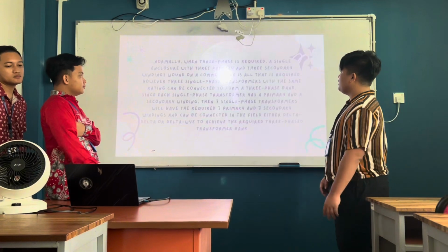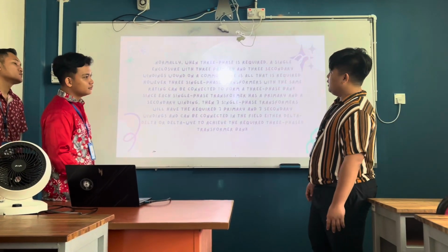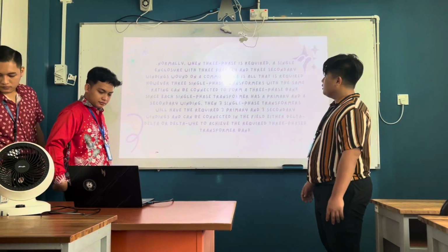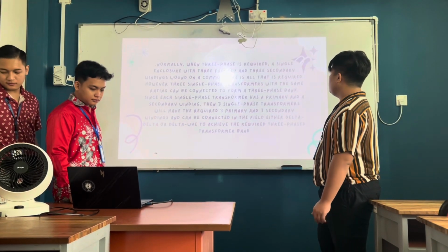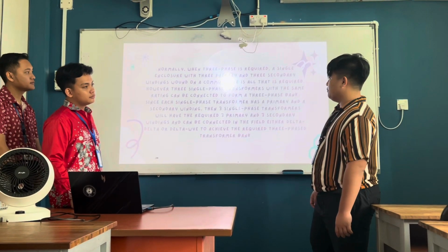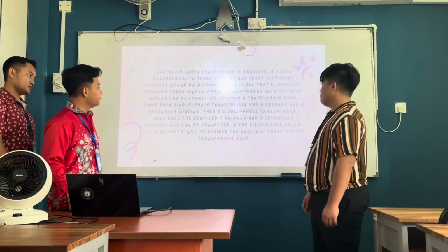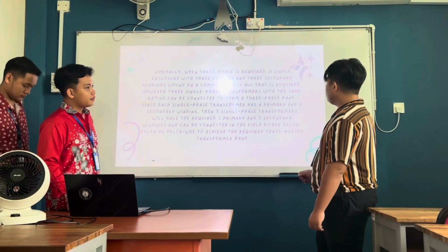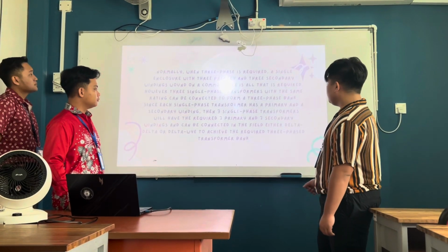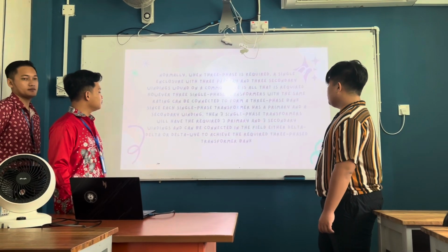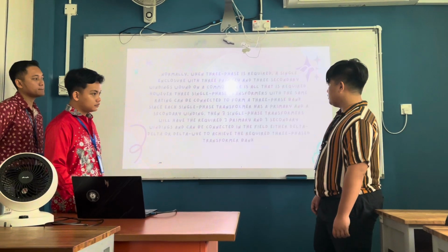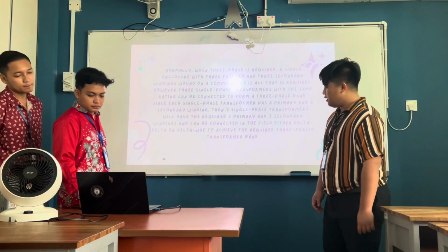Normally, when three-phase is required, a single enclosure with three primary and three secondary windings on a common core is all that is required. Alternatively, three single-phase transformers with the same rating can be connected to form a three-phase bank. Each single-phase transformer has a primary and a secondary winding. Then three single-phase transformers will have the required three primary and three secondary windings.